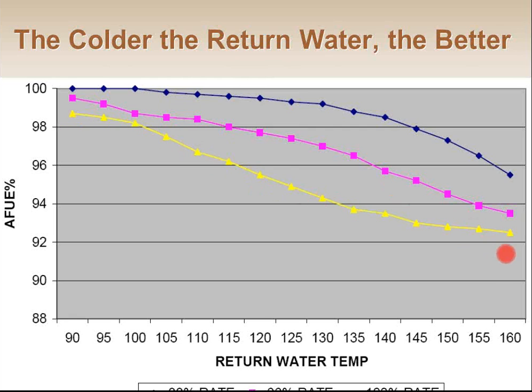The other thing that happens is if I turn the firing rate down, I can get more efficient. So as you can see down here, the yellow is the 100% firing rate. The magenta, purple, pink color, whatever that is, is 2/3 firing rate. And the blue one is 1/3 firing rate. So if I just have a normal 160-degree return water, my boiler, and I turn it down to 1/3, I could pick up, say, another 2% or so efficiency.